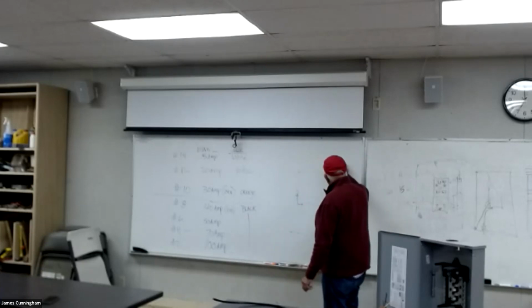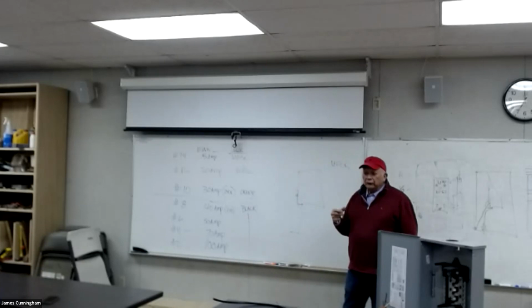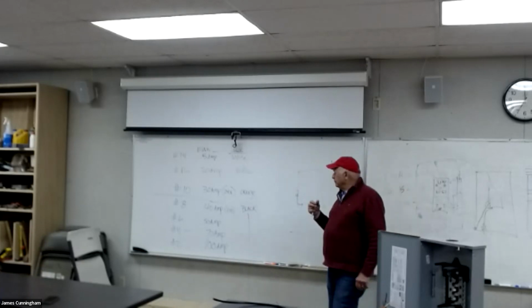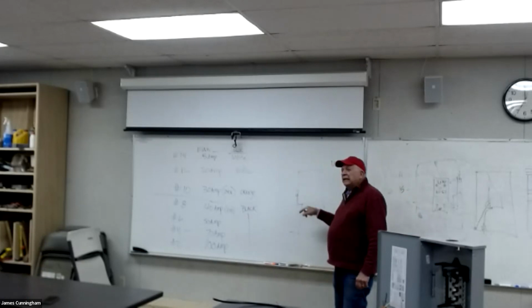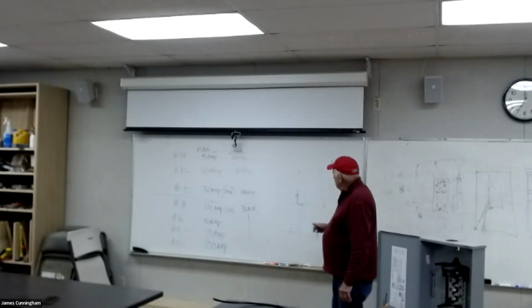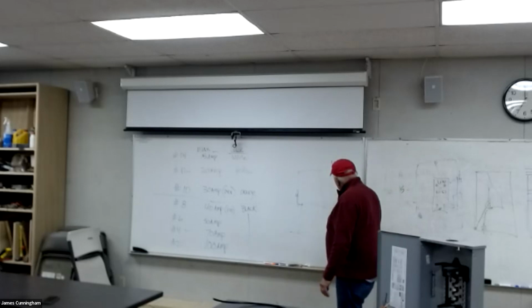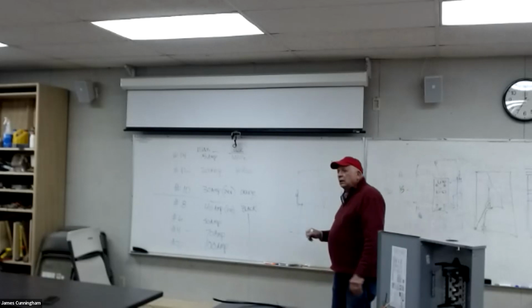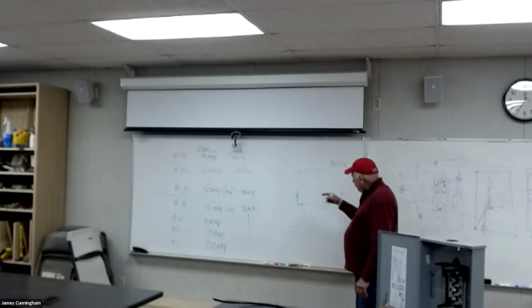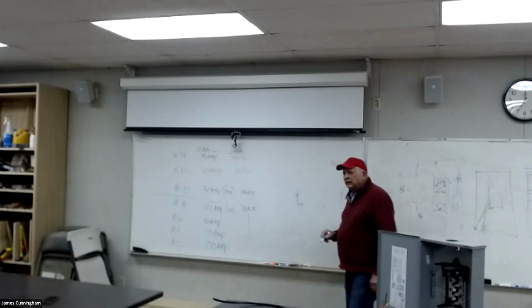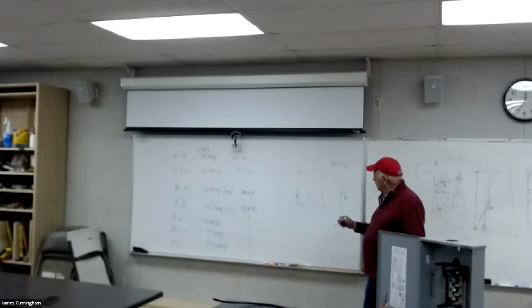So UFER. Now, I call it UFER ground. Some people call it UFER ground. But a UFER ground is when you're doing new construction and you have a concrete footing and you put rebar in that footing. You attach a number 4 solid copper wire with a grounding clamp to it, and the wire has to be continuous. You can't wire nut it, you can't cut it or anything, and that's going to go to my grounding bus bar in my panel.